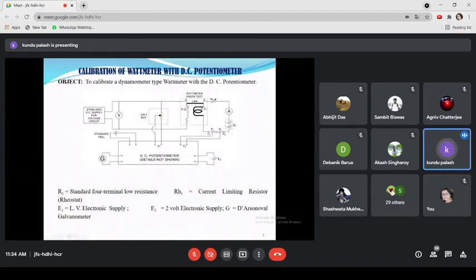This is the phantom loading circuit. So one terminal of the PC and one terminal of the CC should be connected via a copper link. Without the link and with the link, there will be a difference in the test wattmeter. Why? Because whenever you place the link, the potential is common to one terminal of the potential coil and the common terminal, and there will be an electrical coupling. That means this potential will alter the potential of the current coil circuit, and vice versa. Although in phantom loading we set the circuit independently, when the link is placed this circuit is dependent on the other and vice versa. So that will alter not the voltage, but the current coil current.